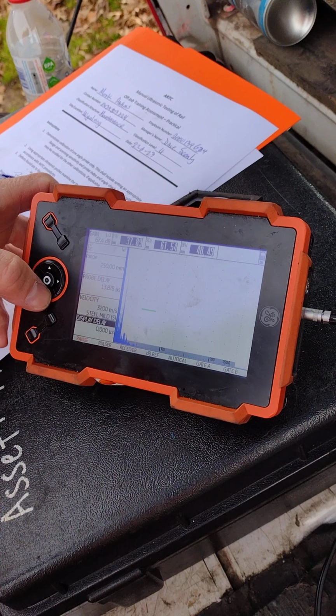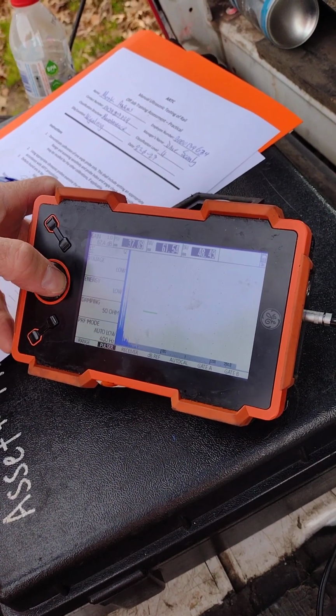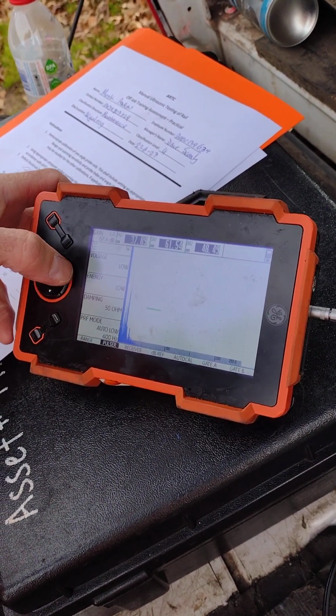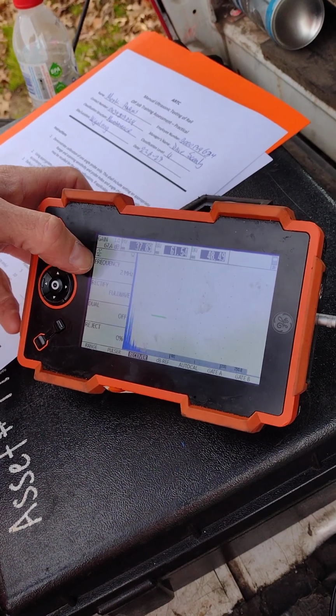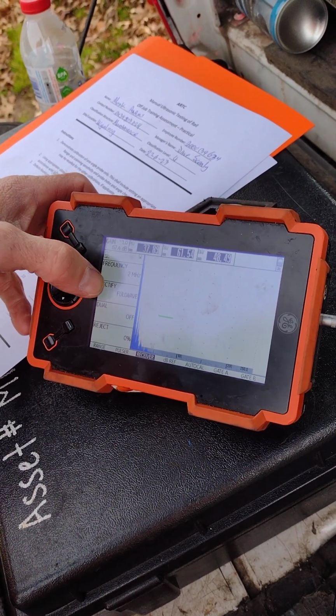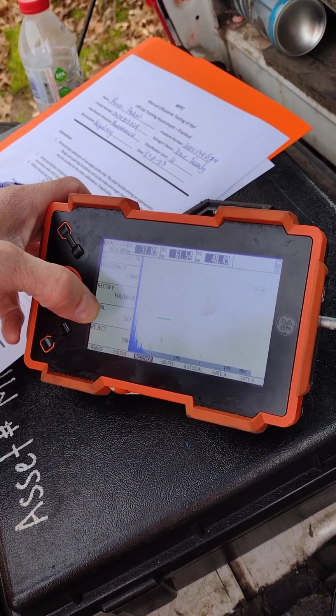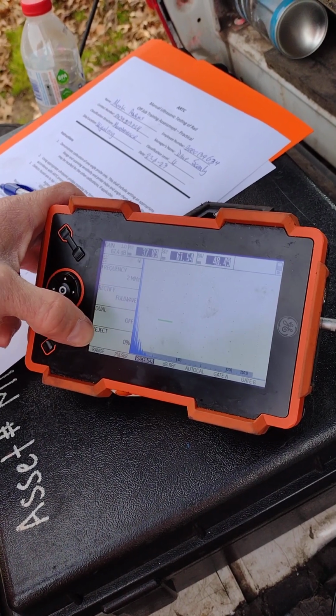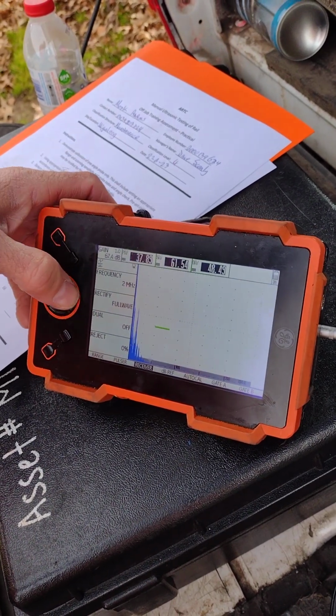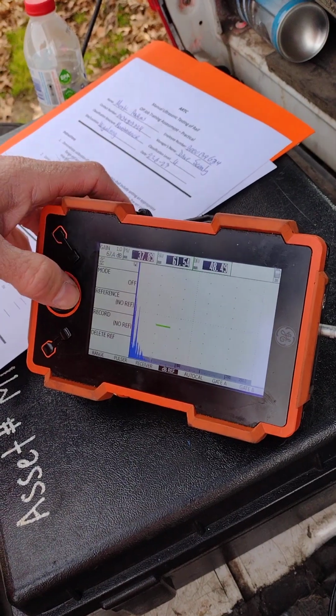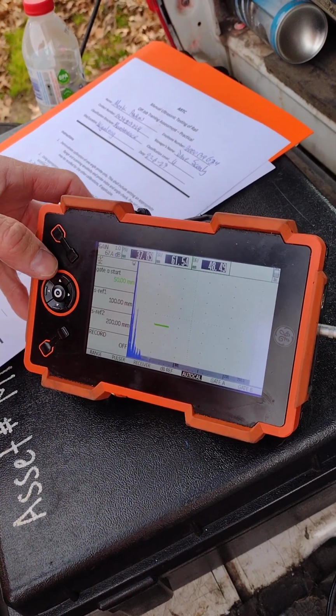We'll then come down to delay, we'll pass through that, we won't change that. Pulser, we'll leave those settings as they are. Receiver, we want to just check we've got a 2 meg probe, that's correct. Full wave rectified dual is off because we've got a single crystal probe, and we never touch reject. dB reference, we'll skip through that, don't worry about that, and then we'll come to auto cal.